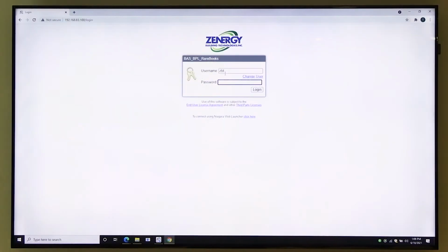So the way the system's set up, we have basically a server up in the, I don't know if it's on the 6th floor or the 7th floor, the mechanical space up close to the roof, in a panel that communicates to all the controllers that we have installed that monitor the temperature and control things like the airflow and the valves controlling temperature and everything. So that server communicates out to all these controllers.